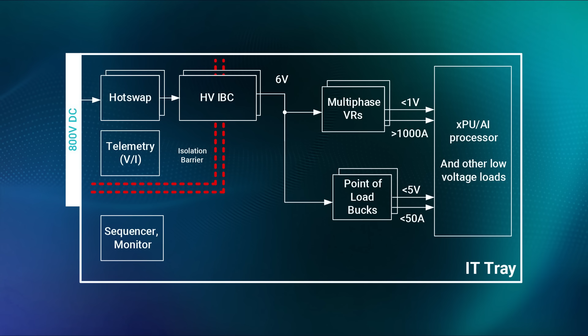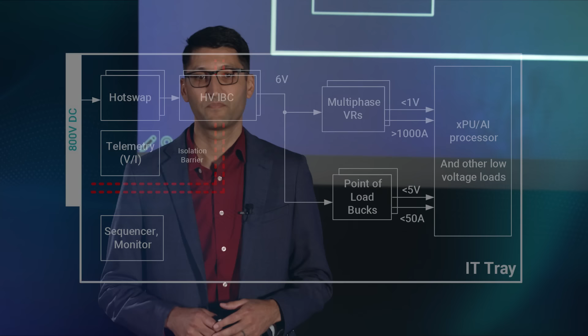Another potential future trend that we see is in the IT tray itself. This approach could be going directly from 800 volts down to 6 volts in a single high voltage, high conversion ratio IBC. Now, the benefit of this is that it enables us to use a lower input voltage to the multi-phase VRs. That in turn enables them to operate at a higher frequency, more efficiently, and with higher performance.